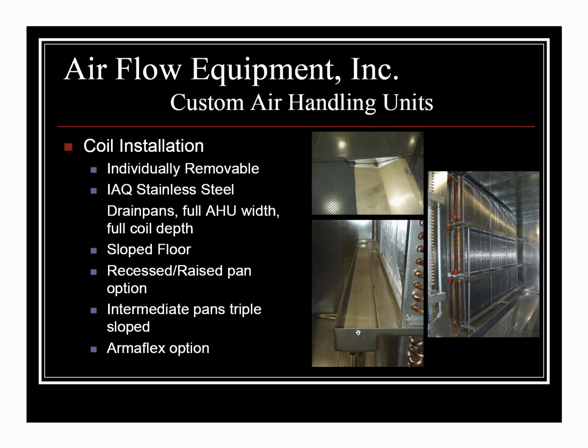Something neat and a bit hard to see in this slide is our intermediate drain pan, which is also positively sloped. This front trough is on a slope and drains down to the coupling, then into the main drain pan. We're very serious about having no standing water in the units, so there's 100% drainage out of the sloped floor sections, the main drain pans, and the intermediate drain pans.